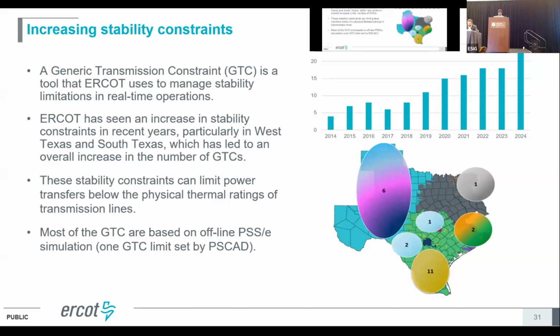Because of this approach, we're seeing more and more of these stability concerns. We started with about 8 GTCs in the past, during CREZ when we began having more wind generation added in the Panhandle area. Now, with solar and batteries coming into the ERCOT grid with more additions, we're at a point where we maintain 24 GTCs in real time — 24 different interfaces where we manage flow based on stability limits calculated in both offline and real-time online studies.